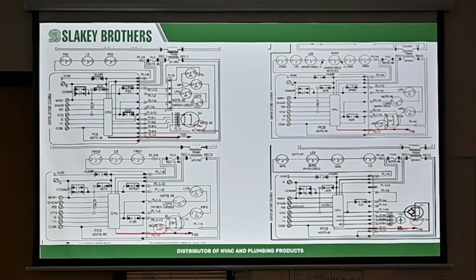So the high efficient, there's a little more to it, which is why it's got a separate ground wire. It wants to protect the ECM and the blower, both of the inducer motors and the ECM motor. So it does have a different, bigger ground wire connection to it overall.